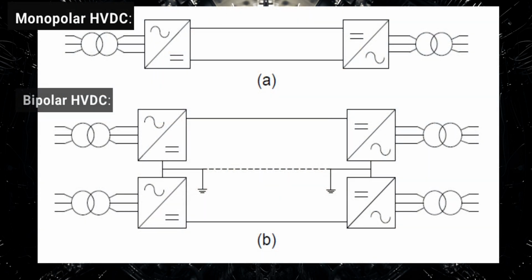The next point is to discuss DC transmission topologies. First is monopole topology. It uses a single conductor, either positive or negative polarity, with ground return. It is cost-effective and commonly used for submarine cables and long-distance transmission, but it lacks redundancy. Bipolar HVDC consists of two conductors, one positive and one negative, with a common ground or neutral. This provides greater reliability, as one pole can continue operating if the other fails, making it suitable for high-power, long-distance applications.